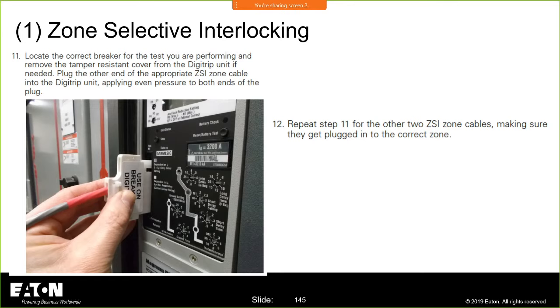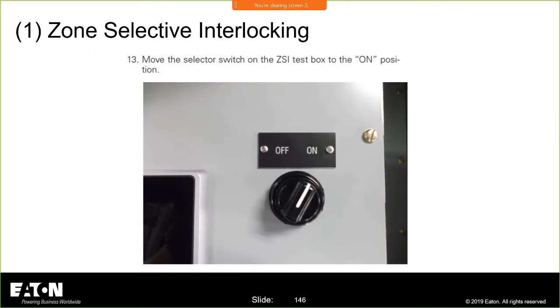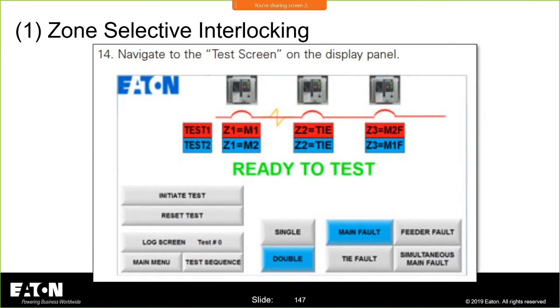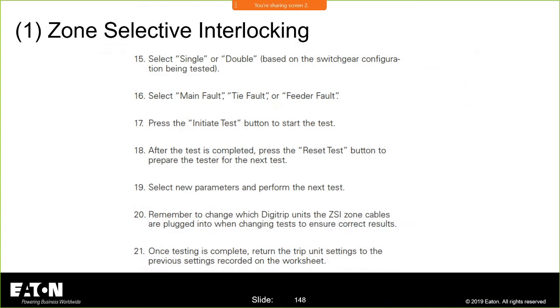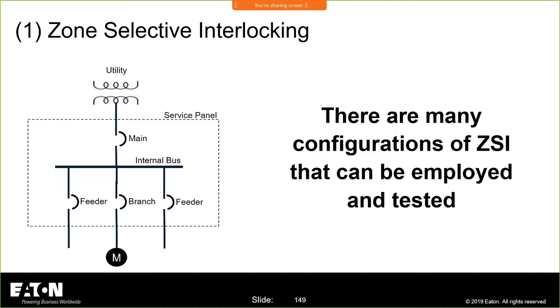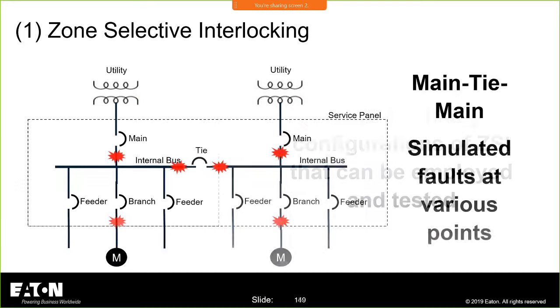There's how you plug it into the face of the breaker. You move the selector switch on the ZSI. So we walk people through simple and complex zone selective interlocking testing, which can be complex. This is the simple method, which shows just a main breaker with feeder breakers. This would be the complicated method. You have a main-tie-main application, and you've got to make sure that all these things work.